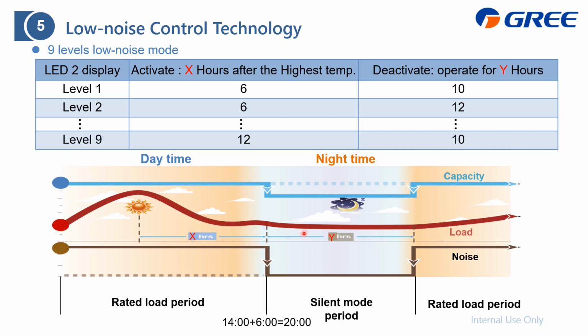And then during the night time, as the outdoor ambient is not that high, the system can lower the compressor output, which is to lower the outdoor unit noise. And of course, this sacrifices the cooling capacity, but during that time, it is okay because the outdoor ambient is not that high. And the other day will be another cycle. So with this preset value, you can choose the best case just for your situation.